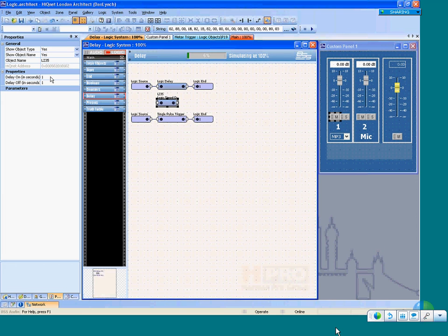With the logic time delay, there's only one cycle, the last one, that matters. So your 10-minute delay could be 10 minutes plus 8 milliseconds, plus 6 milliseconds. It still won't be dead on, but it's going to be way close enough for anything that matters. If you need better than 10 millisecond accuracy, you probably might want to look at something more expensive as a solution.